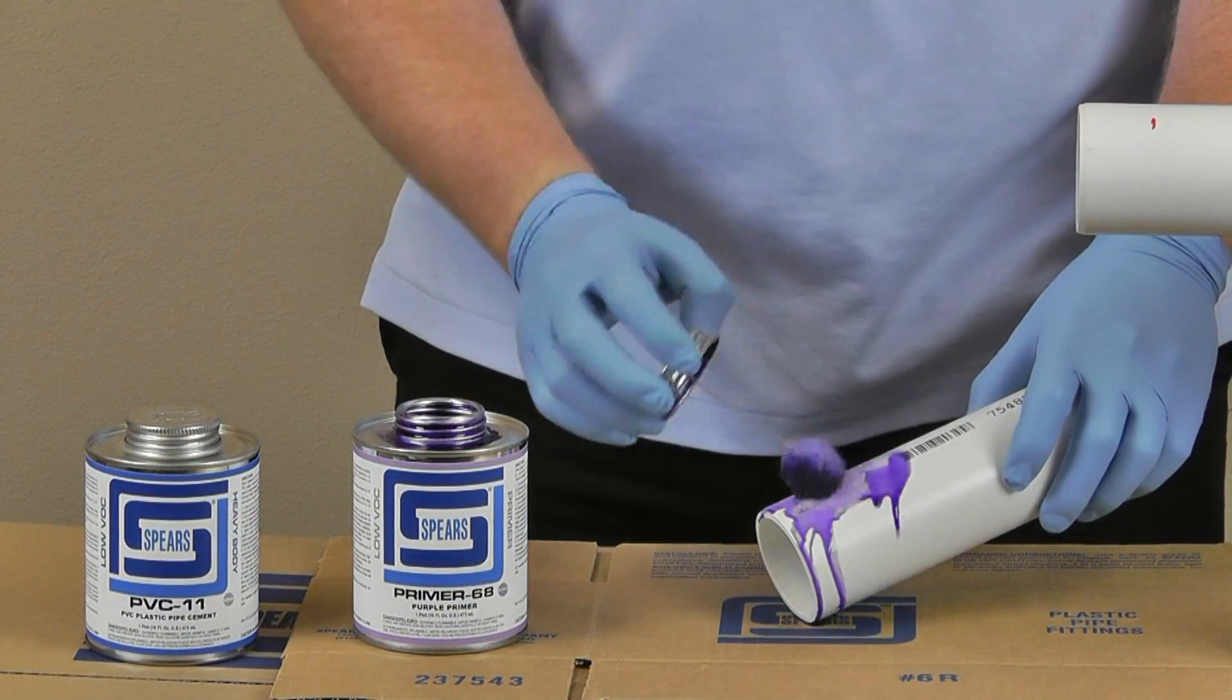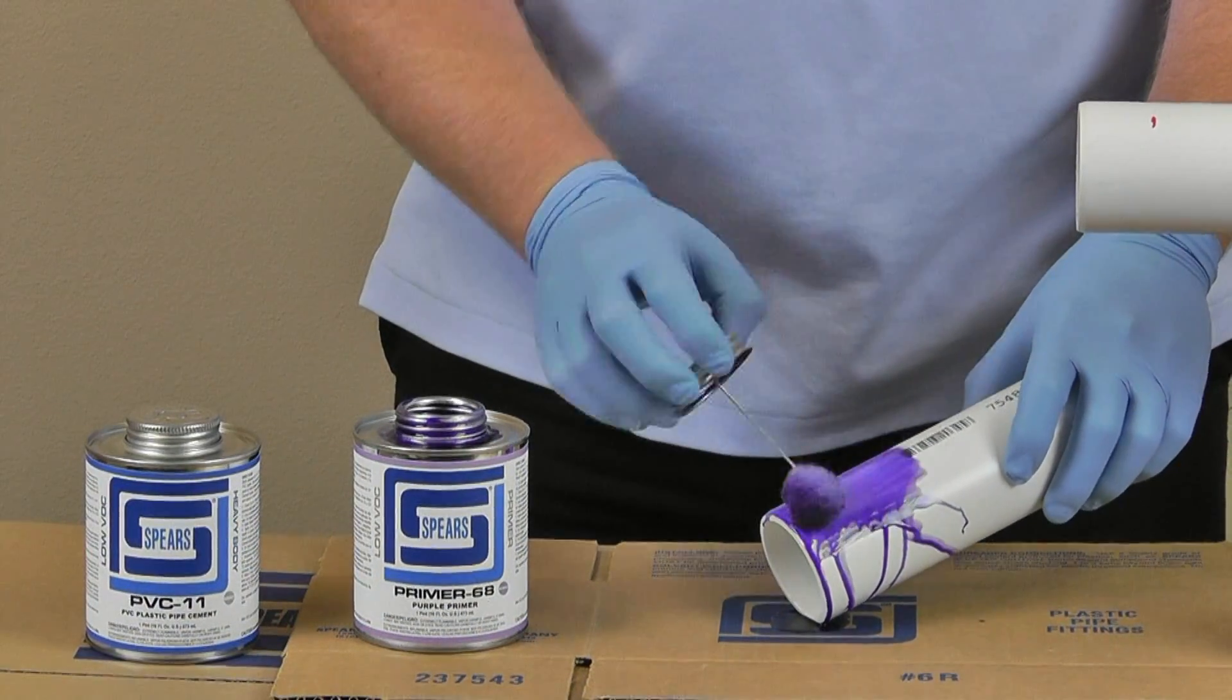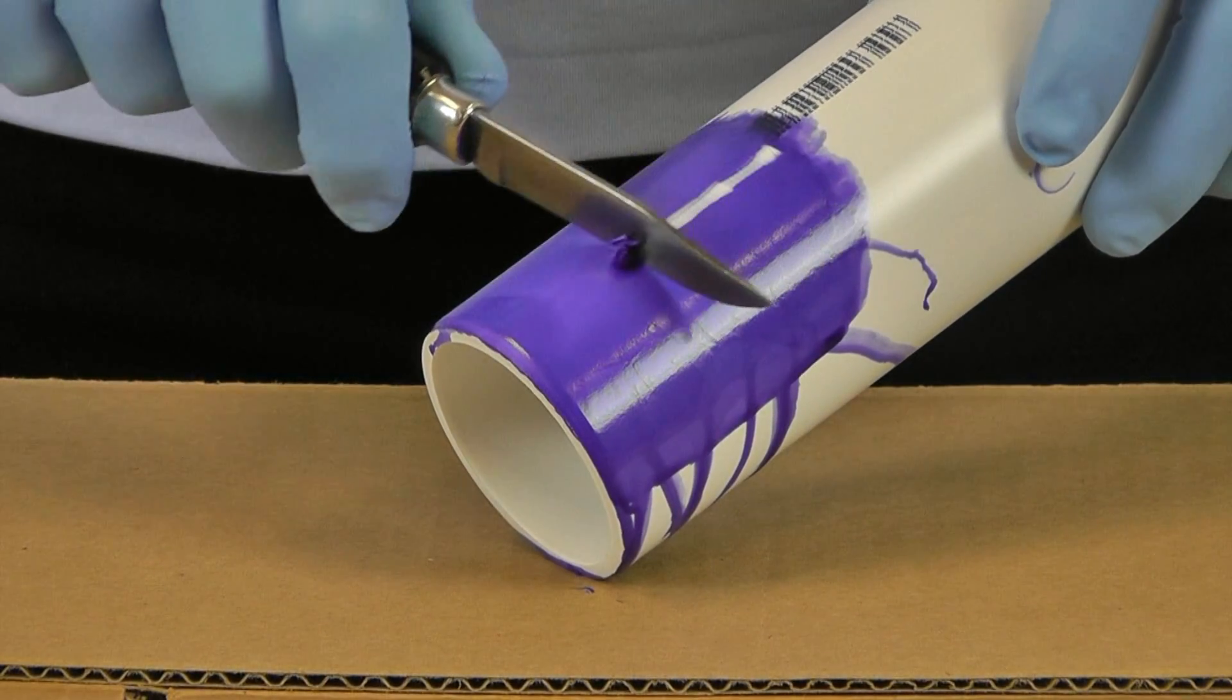Third, on a scrap piece of pipe, apply primer from the can you will be using. To check the softening ability, scrape a thin layer away from the pipe. This confirms your primer is still fresh and suitable for use.